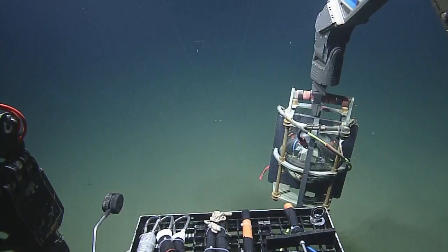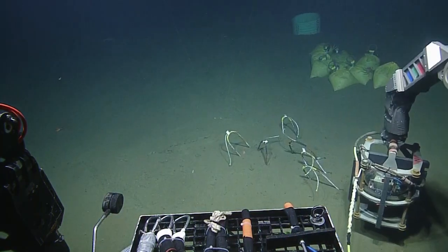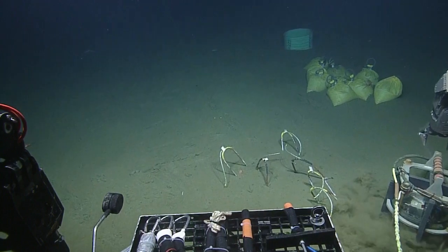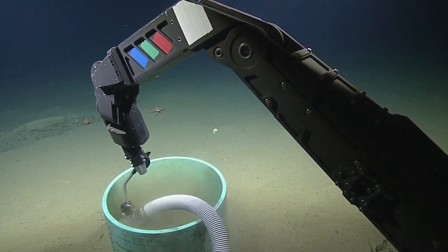What you're looking at is the Titan Accelerometer. It is going to measure plate motion — forward, backward, side to side, and up and down — once it's installed in its location in that green tube.